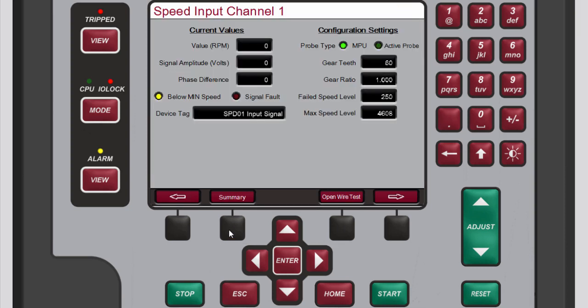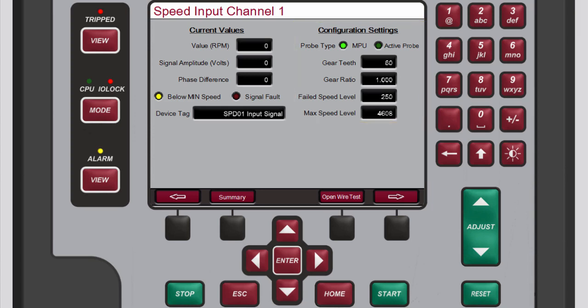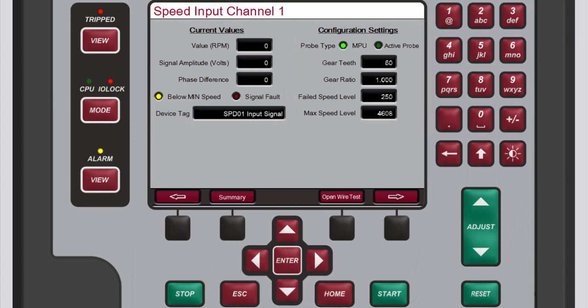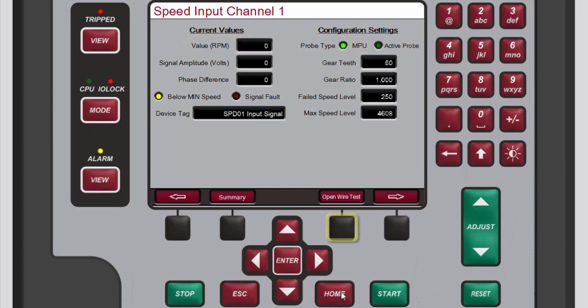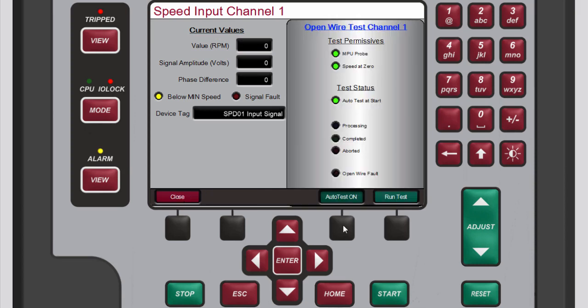The Speed Input Channel screen displays the values we configured earlier in this tutorial. It also displays live values. Verify that the speed is 0 and the probe type is MPU, as this test can be performed only for an MPU when the speed is at 0.